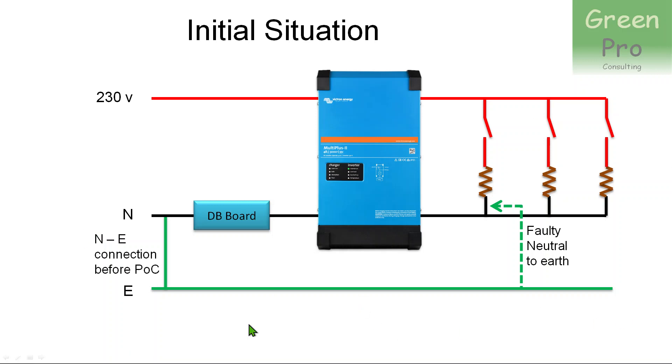There's a bit more of a graphic presentation of that. So we come into the property, you have this connection between neutral and earth, you go into the DB, somewhere in the DB, your main DB, you should be branching out to your inverter. And in the loads of the inverter, what Victron is telling you there's a connection somewhere here between neutral and earth.